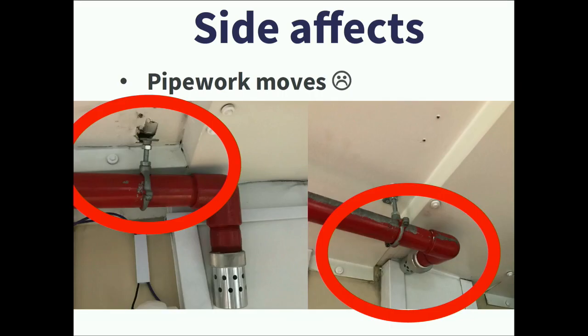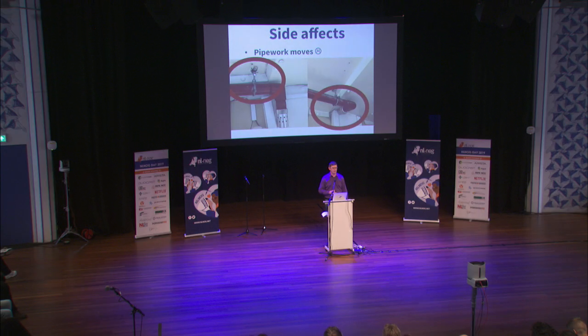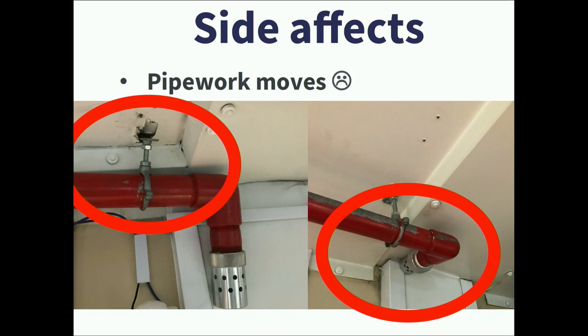Onto the more serious aspects: one reason not to be in the room isn't because the chemicals would cause you damage, it's the high pressure. Cylinders are generally charged anywhere from 100 to 200 bar. When they release, there's a lot of high pressure running through that pipework. If a cylinder or pipework isn't strapped down appropriately, it will move, and these are heavy-duty steel pipes, you don't want to be hit by one. As you can see in these pictures, mountings had ripped out of ceilings and walls, and pipework had twisted just from the force.